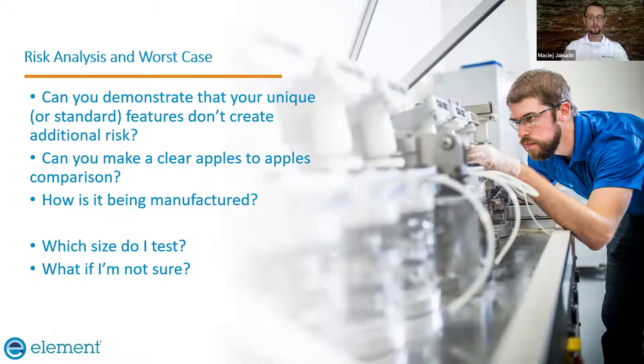It's also important to make sure you have data to back up your worst case. FDA needs to agree, and they're happy to disagree. We've seen a lot of customers that have had issues where FDA has come back and said, have you considered X or Y, or you explained this but you've not addressed this. They'll go back into the database and look at the clinical results and adverse effects of devices with similar features, then come back and say please provide evidence that this feature does not cause this, as experienced clinically. That just creates additional work and delays. So again, think through what the features are and how similar or different they are, and provide the right data to mitigate those risks.